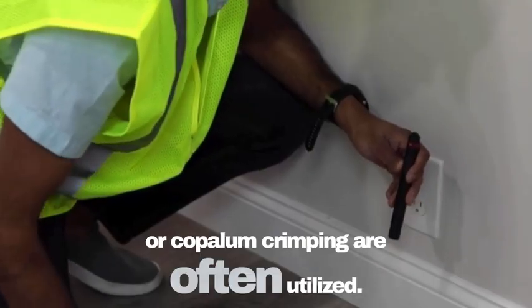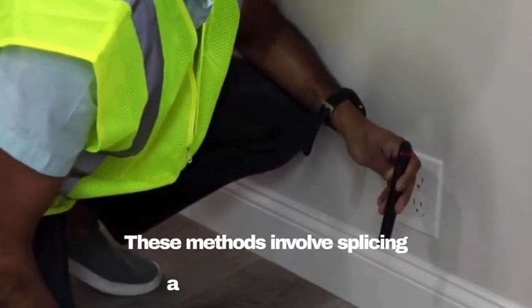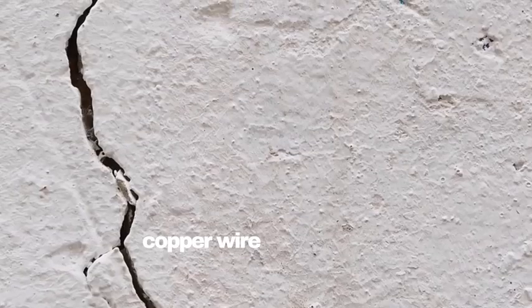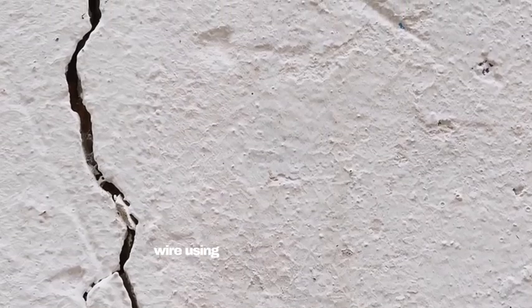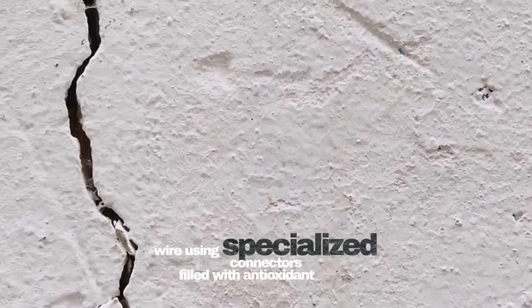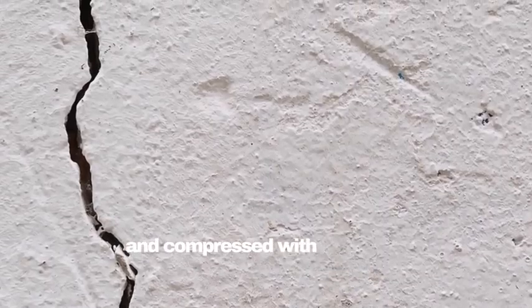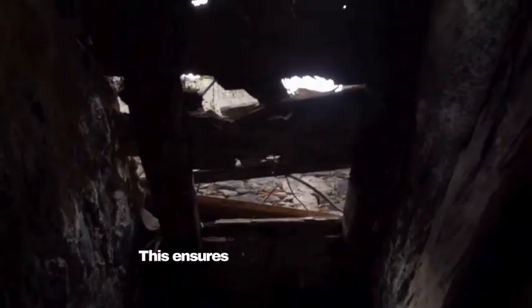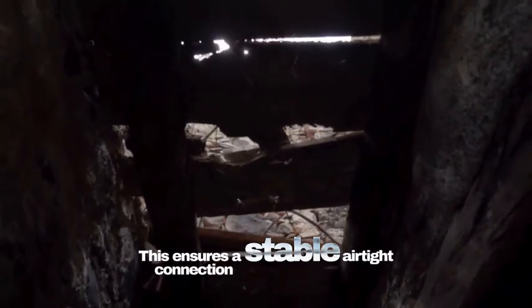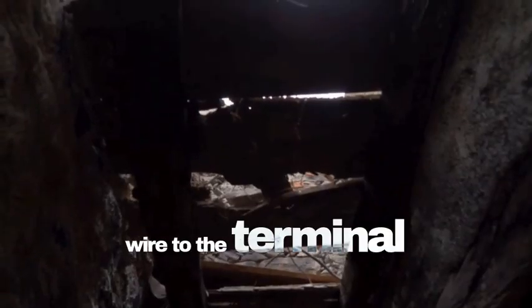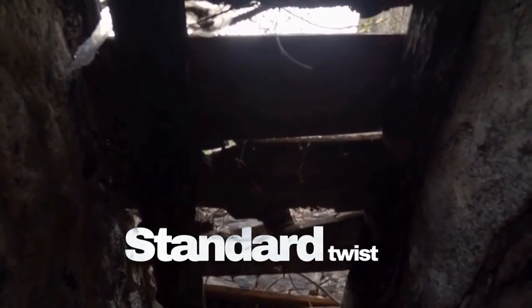are often utilized. These methods involve splicing a short piece of copper wire, a pigtail, to the end of the aluminum wire using specialized connectors filled with antioxidant paste and compressed with high-pressure hydraulic tools. This ensures a stable, airtight connection before attaching the wire to the terminal screws of an outlet. Standard twist-on wire nuts or regular outlets are strictly prohibited on aluminum wiring as they accelerate the failure mechanism.